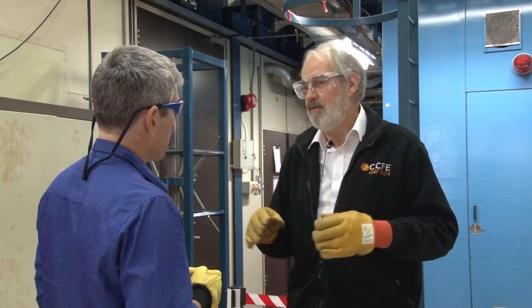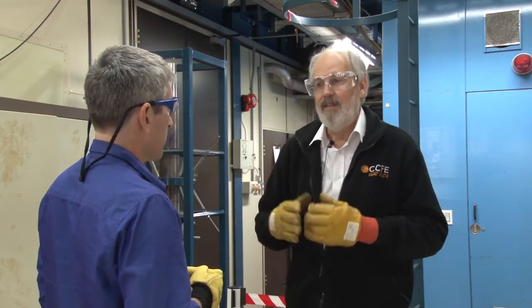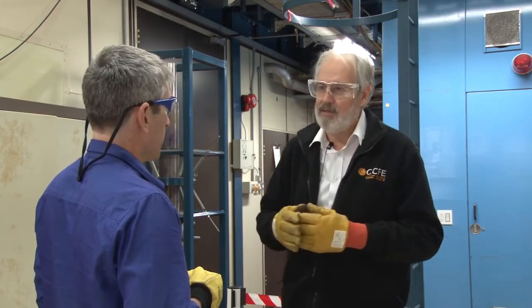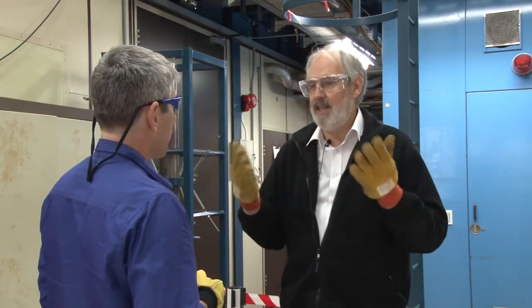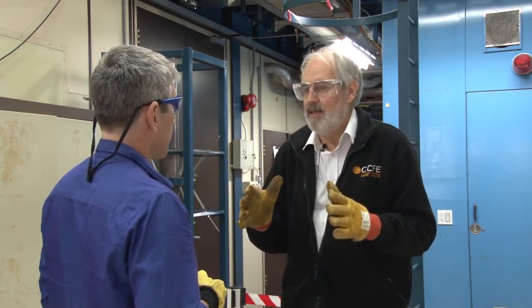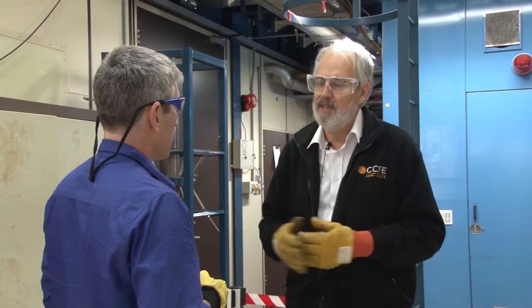You have to keep them around 4 degrees Kelvin. That means liquid helium rather than liquid nitrogen. But overall a much better system. Overall it means we can have a bigger machine with a higher magnetic field, better confinement for the plasma. And that's the whole point of the superconducting side of ITER.